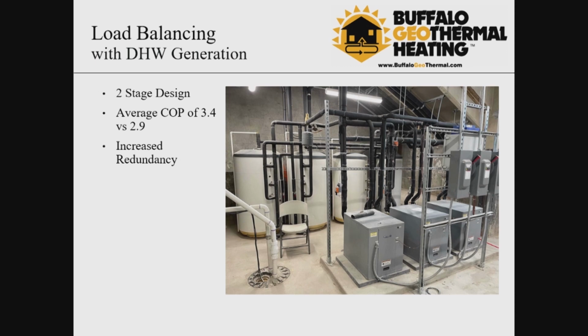Again, the hot water is split into two systems that one feeds the south side of the building, one the north side, and then each system consists of 3 heat pumps and 4 tanks. These tanks are staged, so we have 2 final and 2 preheat tanks, and that enables us to heat the majority of the hot water with a higher COP, and our average COP to make the hot water is then 3.4 versus 2.9 if we would go with a single stage system. In addition, we have an increased redundancy since if even one of the heat pumps fails, the others can take over and continue to heat the hot water.